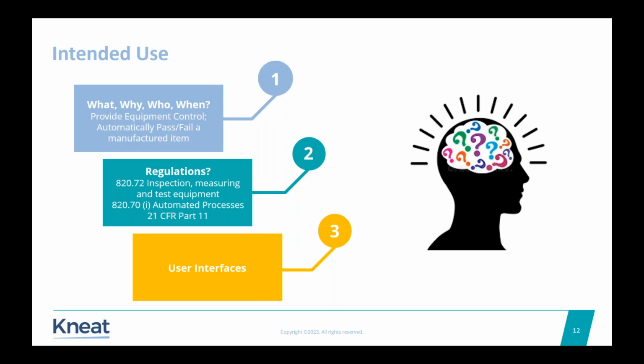Let's say, for example, I'm running a particular system, and it requires me to record my initial and date electronically. So I need to put in my user ID and my password for that particular system. It records that somewhere on a database, right? So let's think about that from a CSA perspective. If that particular part of the app doesn't work correctly, I'm purely thinking of the patient and the quality, the effect on the patient and the effect on the quality of the product. If that doesn't work correctly, that's not going to affect the customer, patient. It's not going to affect the quality of the product. No, it will affect my data integrity. It will affect if I have to do a recall, for example, but that's not necessarily high risk.